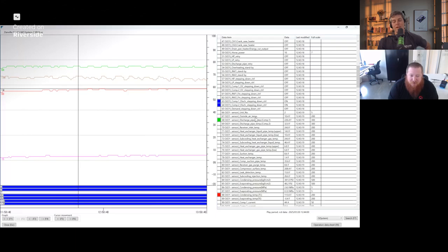Yep, that's it. The other thing you can go to is the outdoor expansion valve pulses. They're pegged wide open. Yeah. What do we know about an expansion valve that's wide open? It's not metering any refrigerant. Yeah, it's not doing anything. It's like, hey, go ahead. I don't care. Whatever. Go ahead. Bob's your uncle. I don't care. And so when you have something like this, this shows me that there isn't any liquid to turn from a liquid to a vapor. Because when you turn a liquid to a vapor, what happens? Heat transfer. You pick up heat.